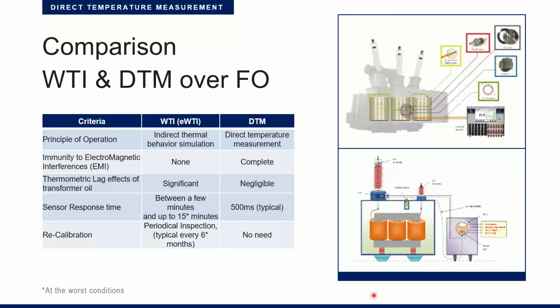With a direct temperature monitor, you're inside the winding in the hotspot area, and you're measuring the hotspot temperature directly. Immunity to EMI: with a winding temperature indicator, there is no immunity. With a direct temperature monitor, or fiber optics, it's completely immune just because there is no current running. It's just light, which is running through the sensor.